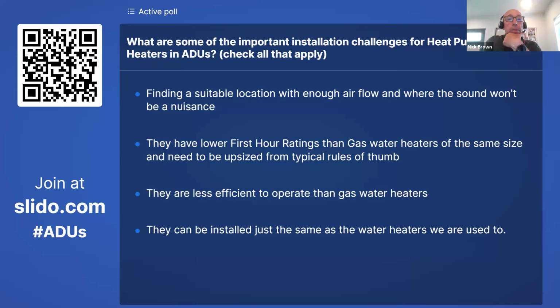Now, there are some heat pump water heaters that are split systems. So instead of having the heat pump on top of the tank integrated into the tank, you have a tank that's connected by water lines to the outdoor unit. Sanco 2 is the most well-known brand. So that could enable you to have a tank of various sizes. The other advantage of a split system heat pump water heater is the noise is outside now. The air source is outside now, so you don't have to worry about if it's in a small closet, will it have enough of an air source, of a heat source? So that might be a solution to you.